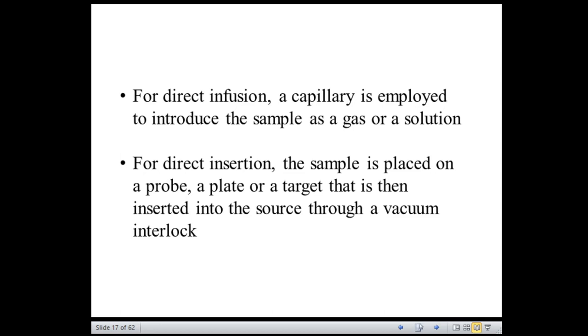Then how to introduce the sample? There are two methods. Number one, the direct infusion method. Number two, the direct insertion method. For direct infusion, as you can read, a capillary is employed to introduce the sample as a gas or a solution.